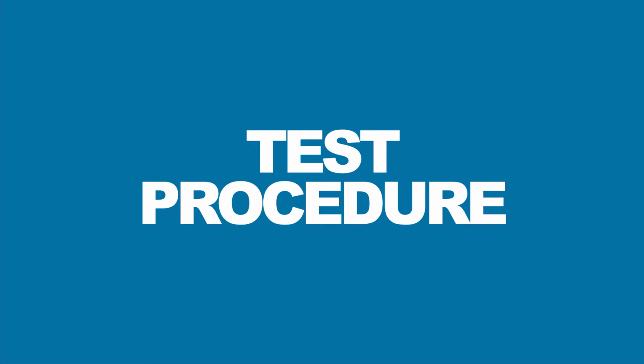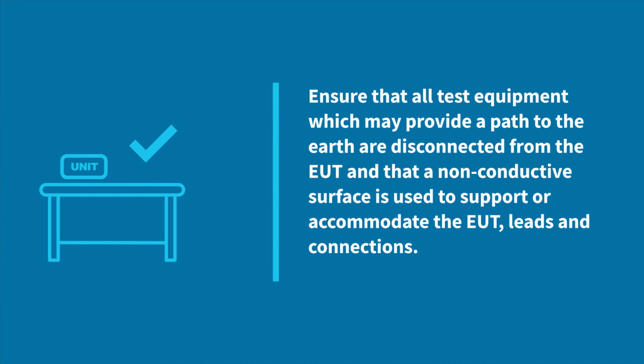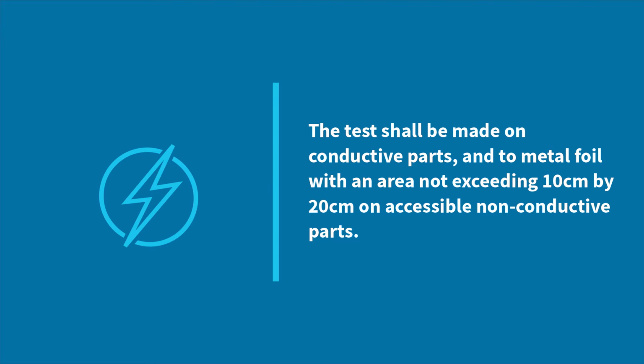Test procedure. Ensure that all test equipment which may provide a path to the earth are disconnected from the EUT, and that a non-conductive surface is used to support or accommodate the EUT, leads, and connections. The test shall be made on conductive parts and to metal foil with an area not exceeding 10 cm by 20 cm on accessible non-conductive parts.